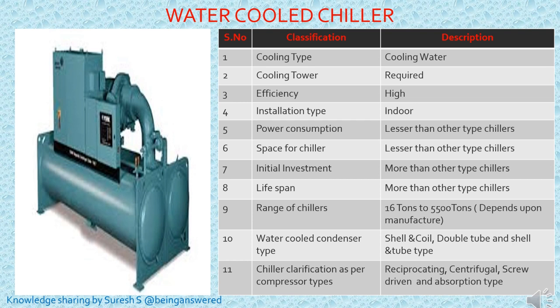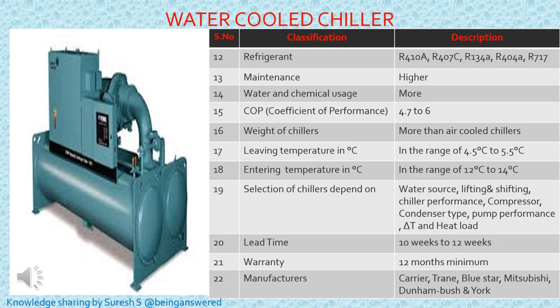For water cooled condenser type, shell and coil, double tube type, and shell and tube type are available. Chiller classification as per compressor type: reciprocating chiller, centrifugal chiller, screw driven chiller, and absorption type chiller. Generally, the screw chiller is the most widely used across many commercial buildings. There are many different refrigerants available in the market: R410A, R407C, R134A, R404A, R717.